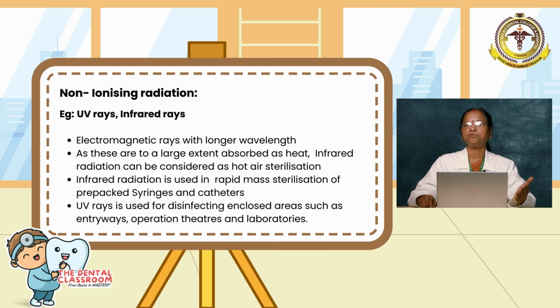Always before you perform work with infectious material, we switch on this UV light, expose for 20 to 30 minutes, then switch off. One very important thing to note: when you are exposing these ultraviolet rays, no operator should be there. I hope you all know the reason: it is carcinogenic.